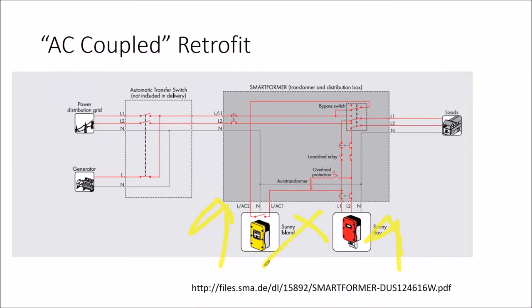If these inverter systems do not communicate with each other, the same grid shutdown protection is used to trick the solar inverter into going offline. The battery inverter sends out a 61 hertz signal through the line, which triggers the UL1741 anti-islanding shutoff of the solar inverter. So even if these are two incompatible brands, the battery inverter can use the safety provisions of the battery-less inverter to control it.